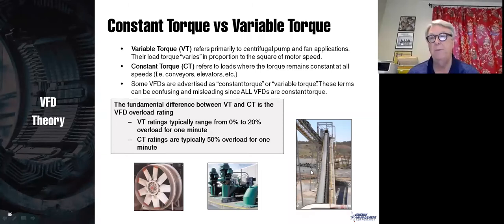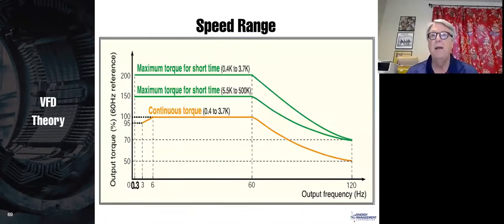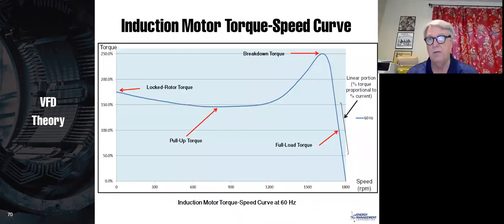A conveyor would be a constant torque application. We'd prefer more like 150% overload. Now, you get constant torque up to 60 hertz, and then once you go above 60 hertz, you can increase the frequency, but you can't increase the voltage because you've only got 460 volts, and therefore the volts per hertz goes down and your torque capability goes down.